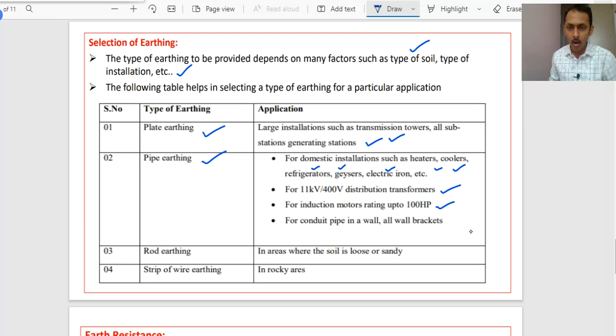For conduit pipe in a wall, for all wall brackets, right, pipe earthing can be preferred. Whereas rod earthing will be preferred in areas where the soil is loose or sandy in nature, and at that time you can go for the rod earthing. And if the area is rocky in nature, then we can go for the strip of wire earthing. So these are the methods for selection of the earthing, right? We have plate earthing, pipe earthing, rod earthing and strip of wire earthing. Depending upon the applications, we can go for the selection, right?